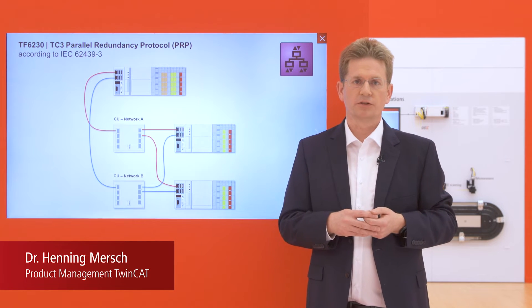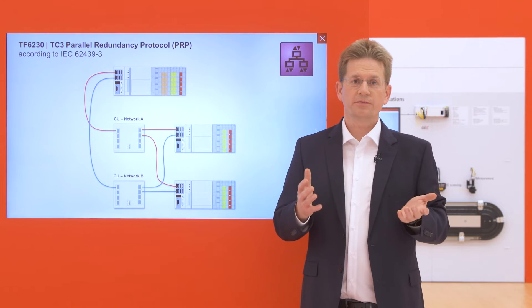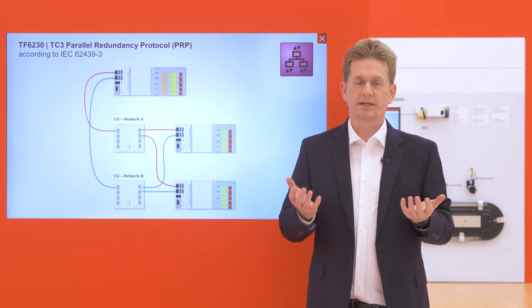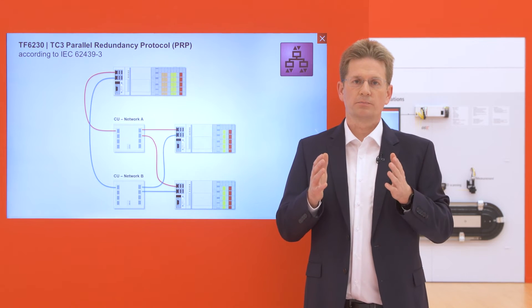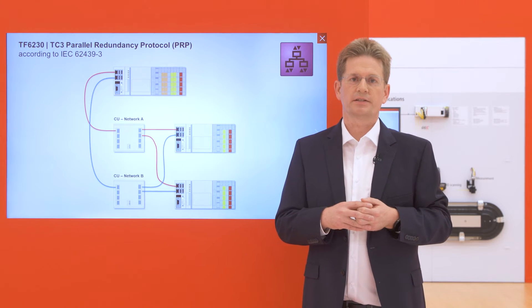TwinCAT PRP provides a software implementation to communicate via a PRP-enabled network. That is a network built out of normal network components, nothing special, but independently from each other. So the traffic goes via both networks from the sender to the recipient and is analyzed there. The TwinCAT system provides a transparent interface for user mode applications, so you don't recognize if it's actually a PRP-enabled network or not.